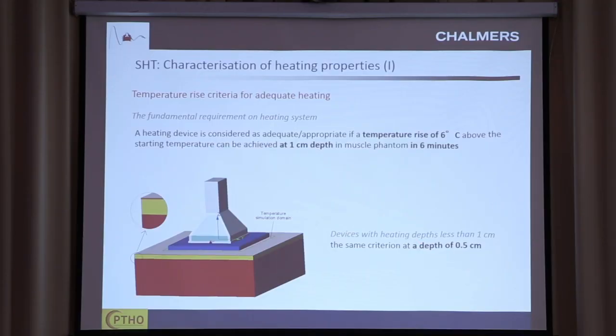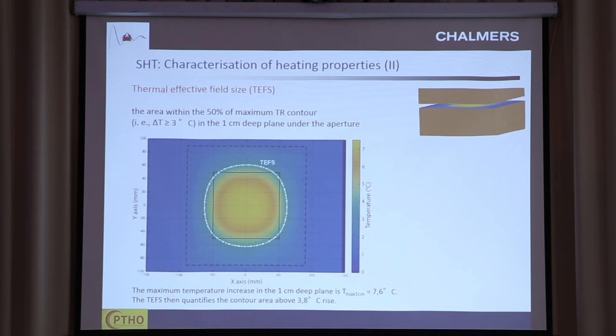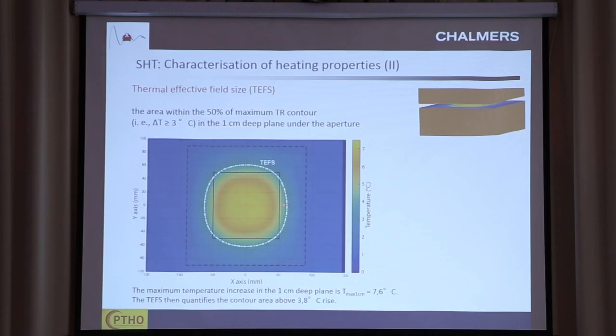For the devices which are more superficial, the criterion is the same, but for the depth of 0.5 centimeters. So based on this fundamental requirement, we can continue with 2 other important parameters, and that's the thermal effective field size. So now we are in a horizontal plane at 1 centimeter depth, as you can see here. We consider the maximum temperature at this depth, and then we draw a contour around the area within 50% of the maximum. In this case, the maximum was 7.6 degrees C, so the contour of 3.8 degrees C gives us the thermal effective field size.